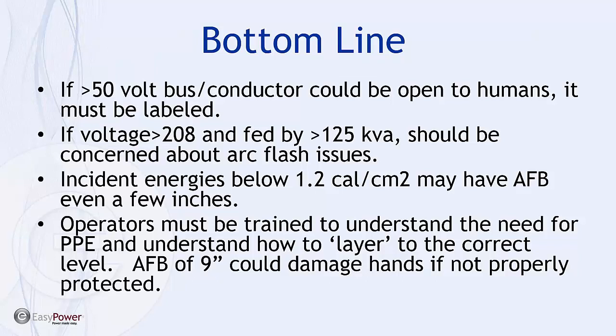Incident energy is below 1.2 calories. Even with just a few inches of arc flash boundary, we need to be aware of the protection involved. This emphasizes that operators must be trained to understand the need for arc flash PPE, and when we show incident energy and working distance on a label, we should discuss routinely, in a safety meeting type environment, what PPE level is needed and how to layer up if it's an elevated category.